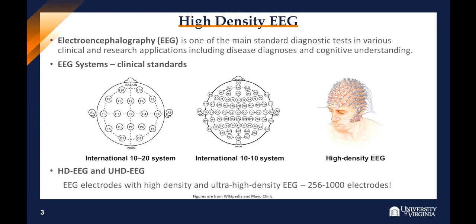The left figure shows the International 10-20 system. The middle one has a higher density of electrodes, which is called the 10-10 system. They are the two common electrode placement methods with the names of all electrodes shown on the scalp. The 10 and 20 refer to the fact that the actual distances between adjacent electrodes are either 10% or 20% of the total front-back or right-left dimension of the skull.